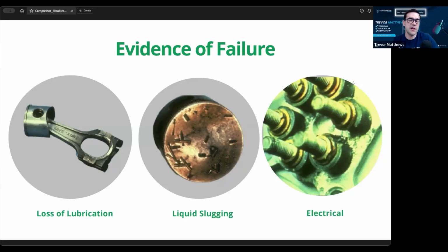But on the electrical side, I think there are some things using your meters that a lot of technicians don't know enough of. I think they know how to do the winding resistance quite easily, matching it up, shutting it off safely, locking out your power, and then double checking with your meter so that you've got no voltage before you touch those wires and take them off, and then they can go and do the resistance. But let's talk a little bit about electrical troubleshooting and compressors, what you see and what you hope more technicians could jump on to look for before deeming a compressor failed.